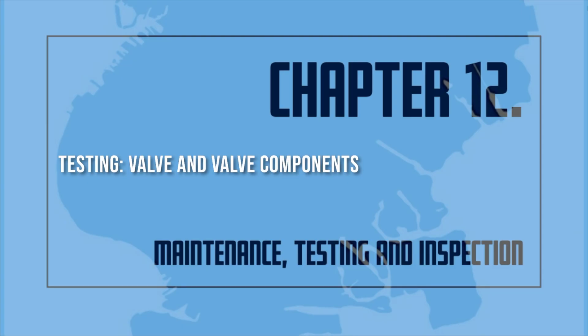4. Testers at the dry pipe valve note the air pressure at which the valve trips and note the tripping time. 5. Testers at the inspector's test note the time at which water flows steadily from the test connection. This time is noted for comparison purposes to previous tests and is not meant to be a specific pass-fail criterion. Note that the National Fire Protection Association No. 13 does not require water delivery in 60 seconds for all systems.